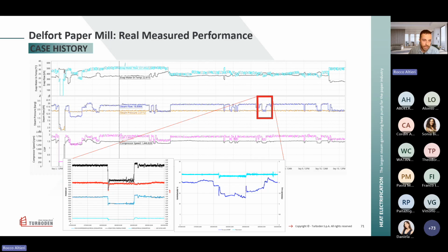You can see here that this was done quite quickly. In a few minutes, the unit was able to adapt to this request, keeping basically the COP constant, because the red line is the COP. So you can see here that also in partial load conditions, the heat pump and the MVR are able to provide the nominal efficiency. In the last two lines here, you see the electrical consumption of the two compressors. The first is the heat pump compressor. The second is a steam compressor that was also adapting very quickly.